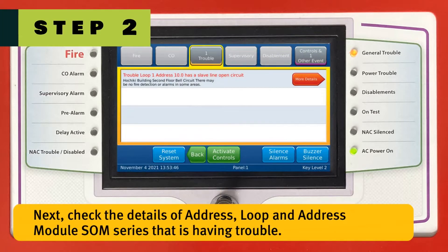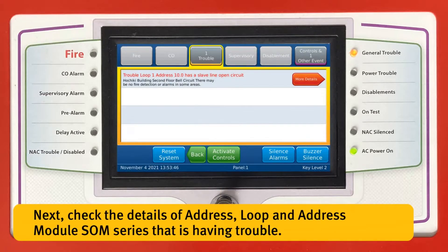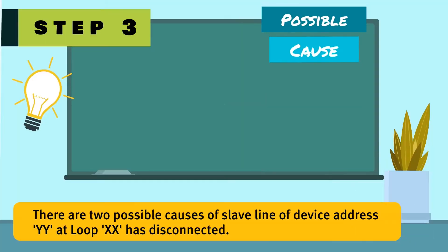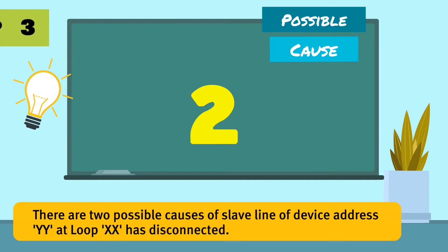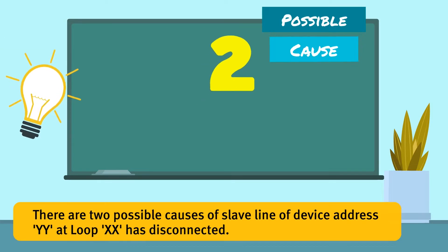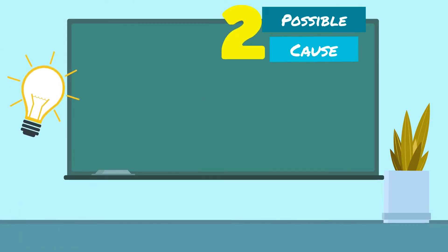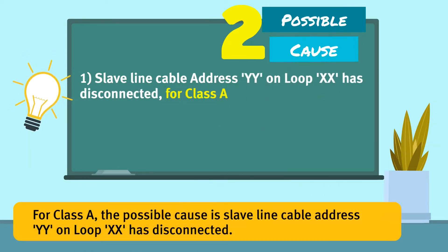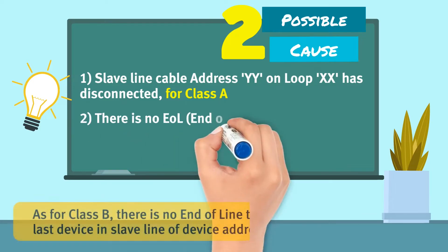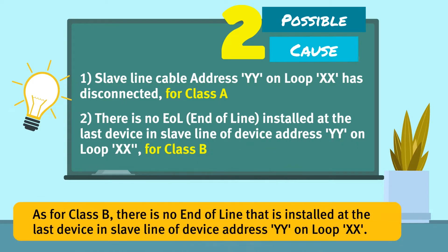Next, check the details of address, loop, and the address module SOM series that is having trouble. There are two possible causes of slave line of device address YY at loop XX being disconnected. For Class A, the possible cause is the slave line cable at address YY on loop XX has disconnected. For Class B, there is no end of line installed at the last device in the slave line of device address YY on loop XX.